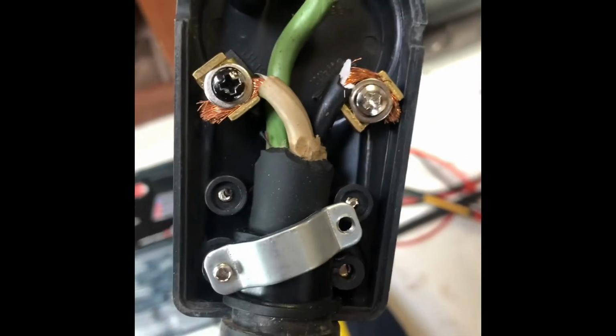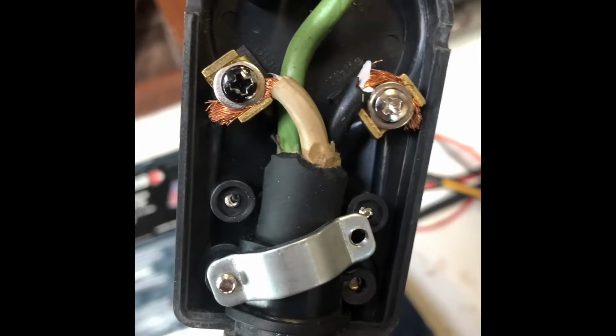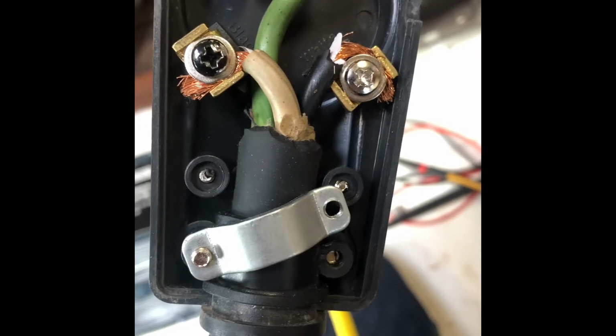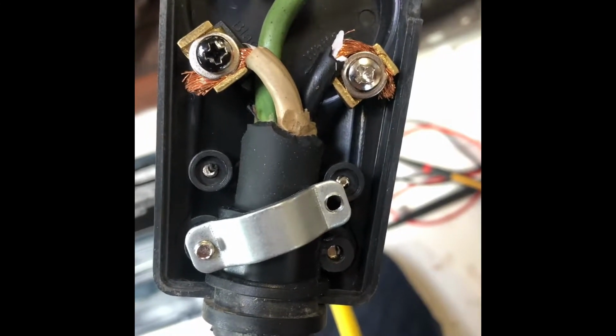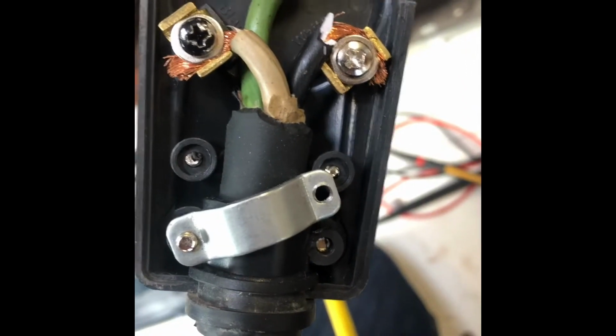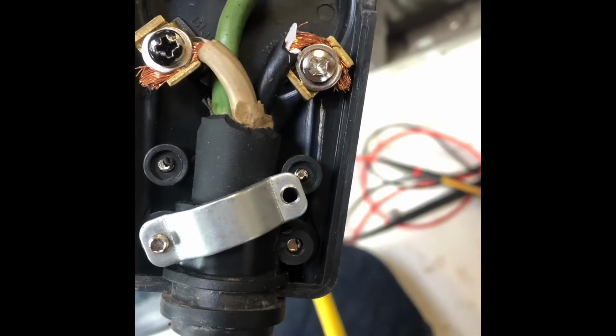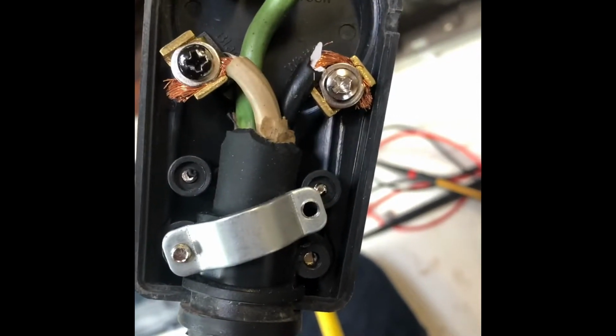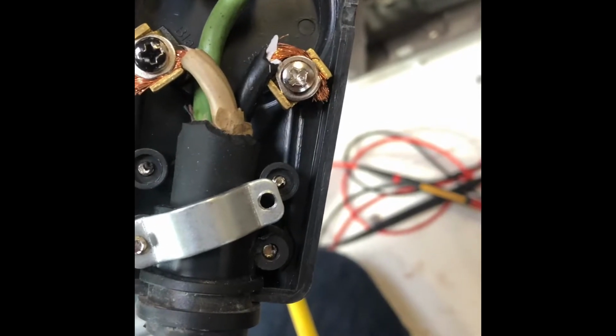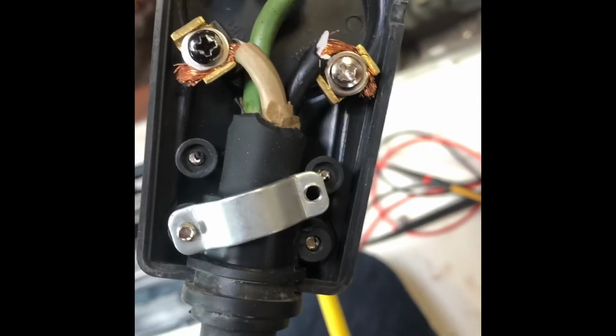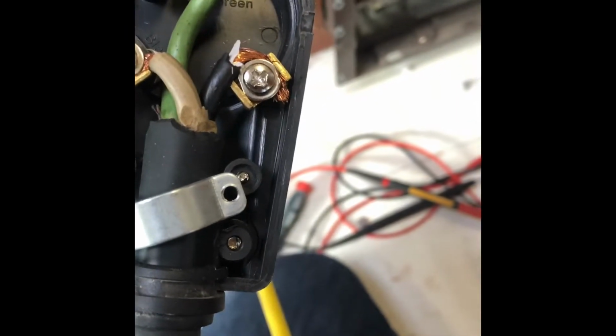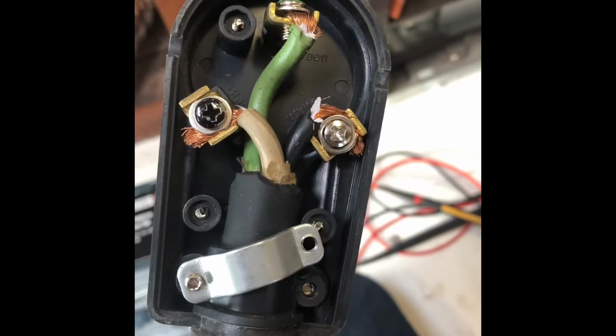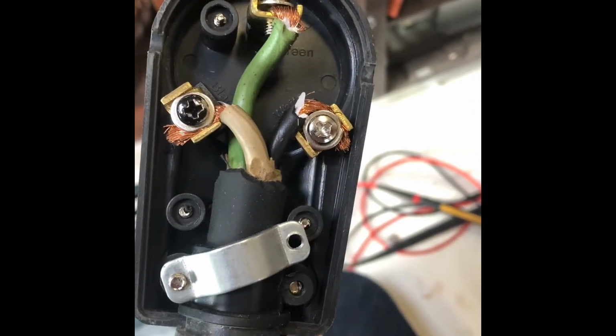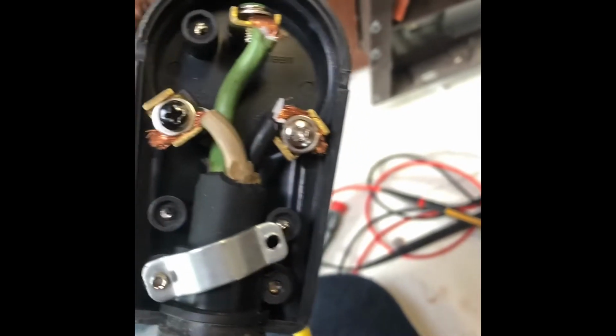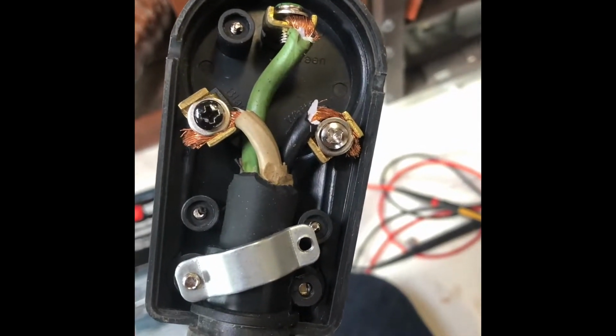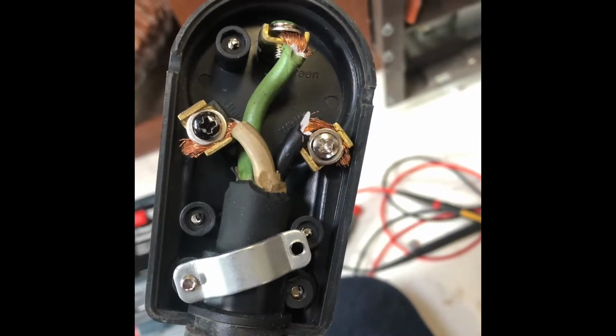In here, if you look, it's quite plainly labeled white and black, and somebody has gone and hooked this plug up with the white on the black side and the black on the white side. So now our polarity is reversed, which means we are getting power to ground or neutral, we are getting voltage there, which leads to a danger for anybody working on it. It's pretty common to happen - it happens in houses quite a bit, where plugs are wired backwards and power comes out of them. But this happens to power the whole unit, so the whole unit is powered backwards.